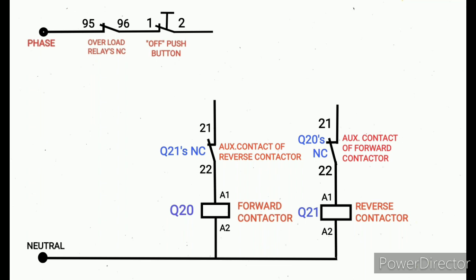Now the interlock is fulfilled, because if forward contactor gets picked up, the reverse is not allowed to pick up. If the reverse contactor picks up, the forward is not allowed to pick up.